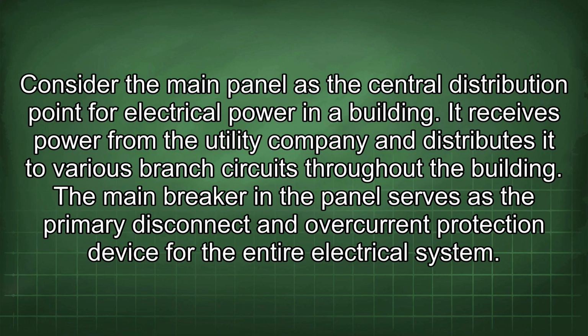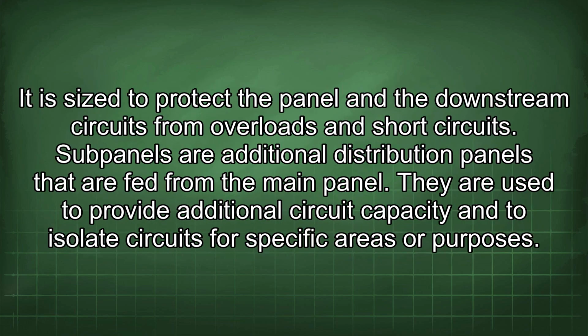Consider the main panel as the central distribution point for electrical power in a building. It receives power from the utility company and distributes it to various branch circuits throughout the building. The main breaker in the panel serves as the primary disconnect and overcurrent protection device for the entire electrical system. It is sized to protect the panel and the downstream circuits from overloads and short circuits.